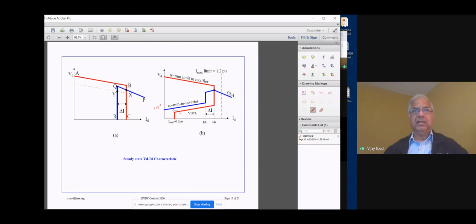And finally, we have this modification over here, which is the minimum current setting, which is typically around 0.2 per unit. This is again a minimum limit which the valves do not have. The valves do not like having current zeros. So what happens is if the current in the DC system takes up this kind of approach, we have harmonics on the current and we have current zeros taking place over here. So we want to make sure that this minimum current is above this value, so we don't get these current zeros due to the harmonics in the DC current.